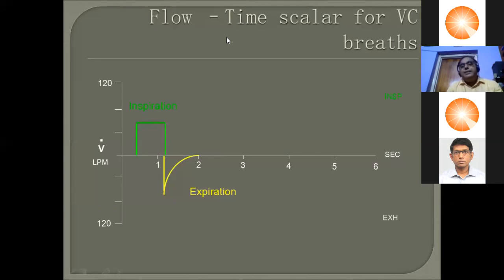So that is about pressure control. And now let us talk about volume control. In volume control, we'll consider the flow time scalar first. So what happens in volume control? You dial a tidal volume and you dial an I time. Suppose you have dialed an I time of 1 second and a tidal volume of 500 ml. As you do that, the machine does the math: okay, 1 second, 500 ml.